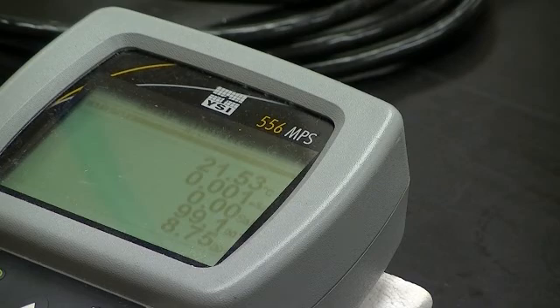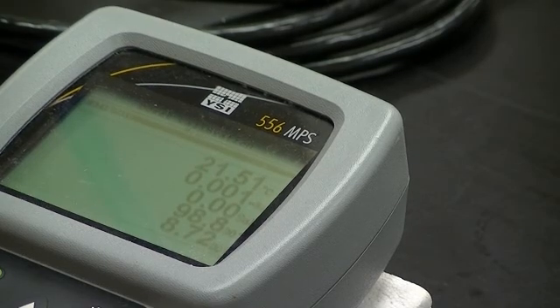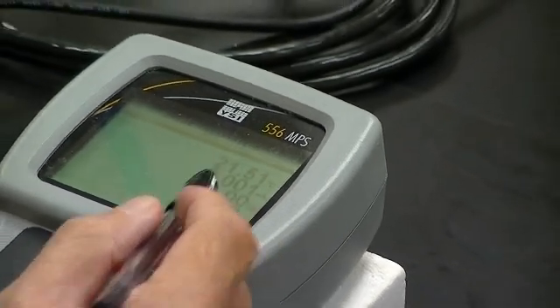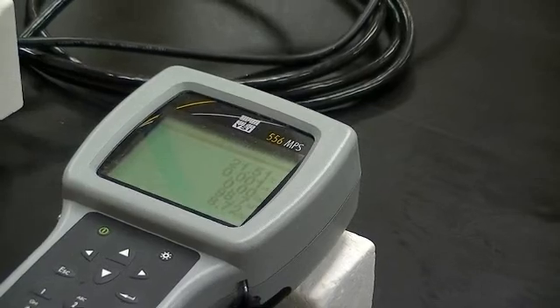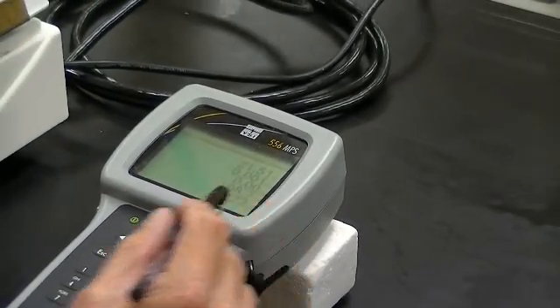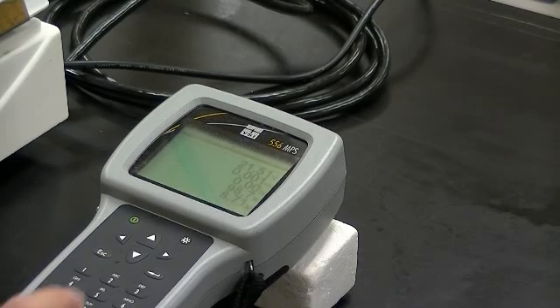Now it says 99.1, 99.0, 99.0 going once, 98.9. Okay, now this is another one of these cases where you would let it stabilize completely. For the sake of the video, I'm going to calibrate it right now. But when the lower two numbers stop moving, it says 98.7% DO. It's pretty close. You hit the return key again.